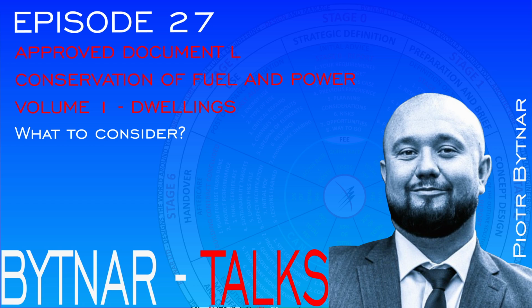Commissioning information needs to be provided to the dwelling owner and should include the details of the fluid and its commissioned concentration. For community heating systems, they should be commissioned to optimize the use of energy for pumping and the flow rates. Individual heat emitters should be balanced either using calibrated control valves or appropriate return temperatures. Underfloor heating commissioning should be done to BS EN 1264 Part 4.